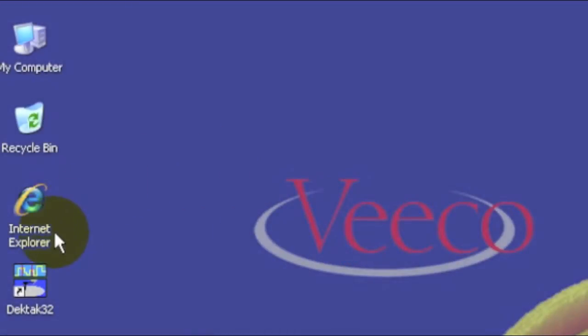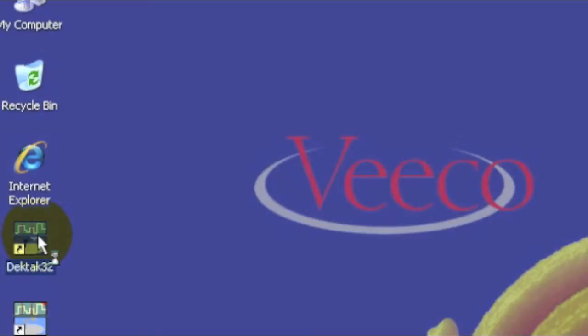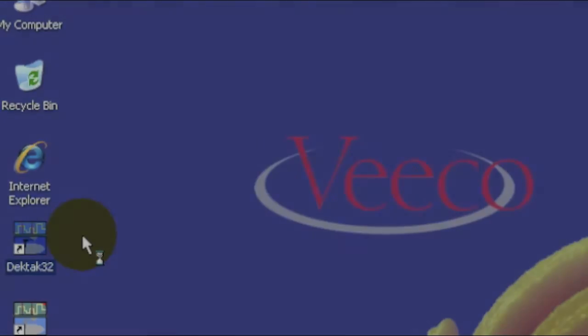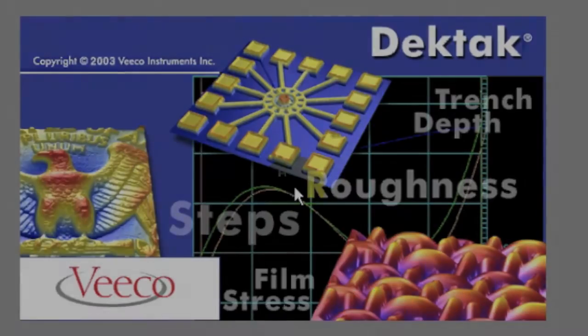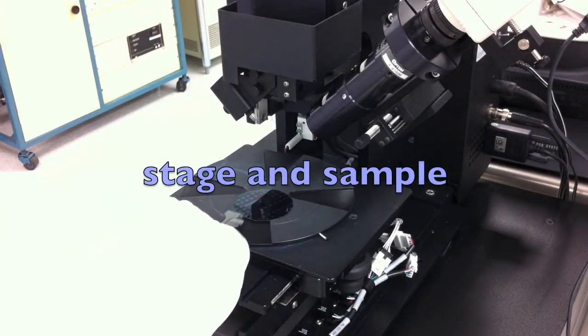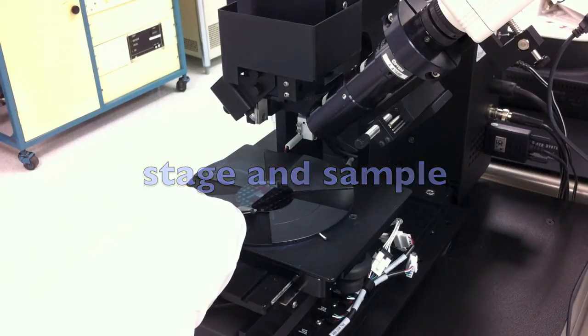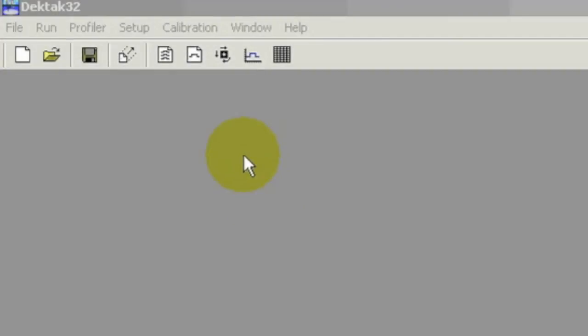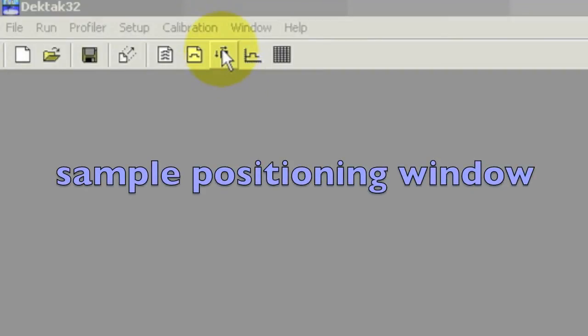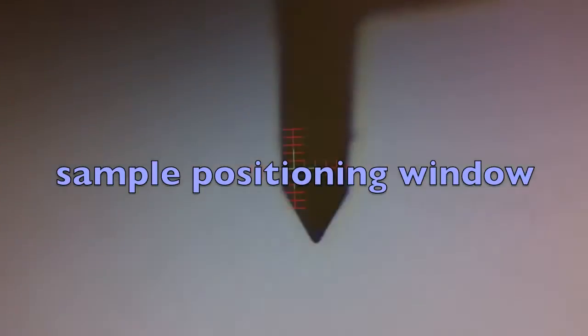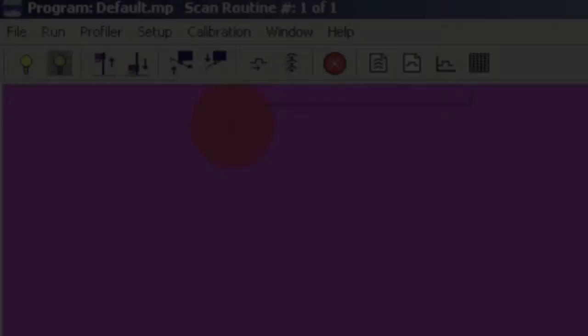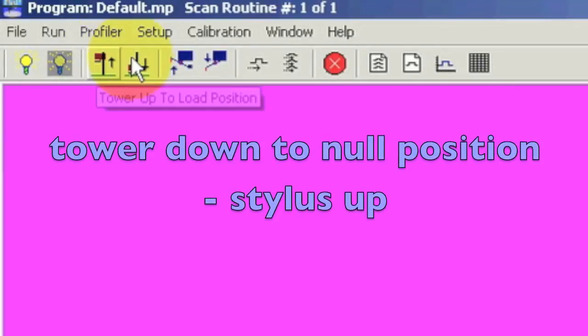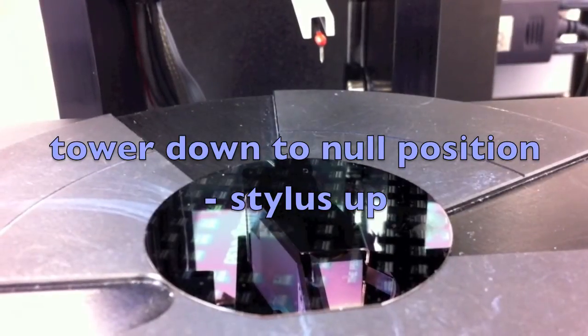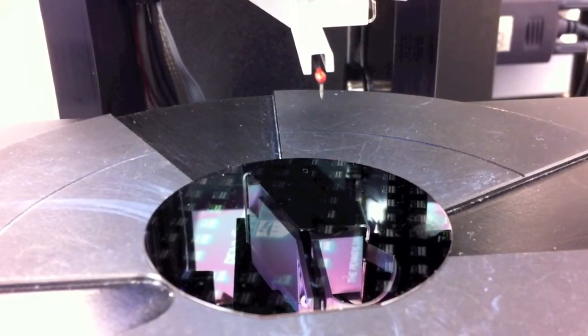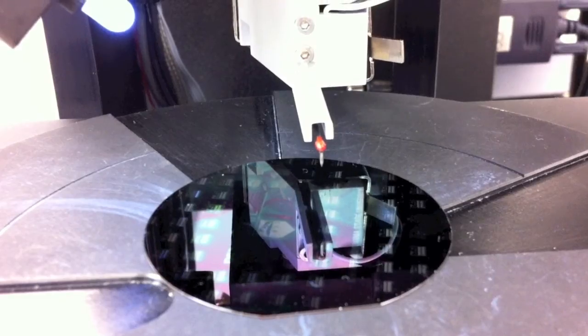Using this tool requires some integrated software. Start by double-clicking the Dektak32 icon. Once the software has loaded, load a sample onto the center of the stage as previously shown. Now click on this icon, the sample positioning window. This switches to a view from the optical microscope. Next, click this icon, tower down to null position stylus up. This will bring the tower and probe down to your sample, but will leave a small gap between the probe and sample so that you can make fine adjustments to the stage.